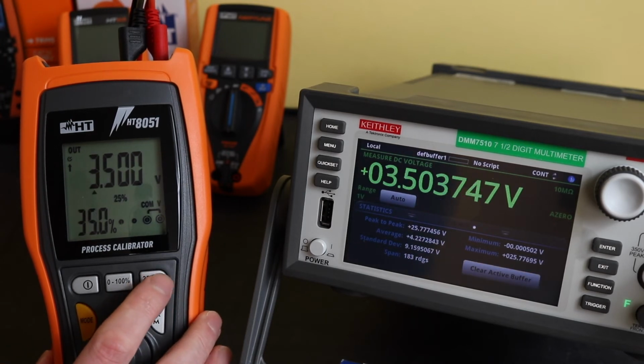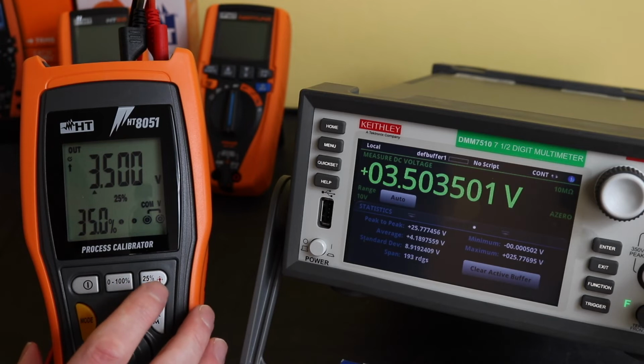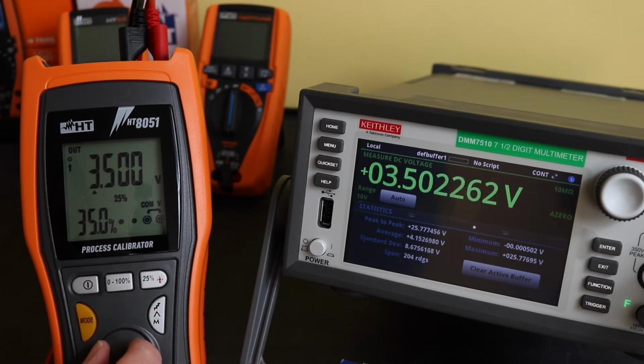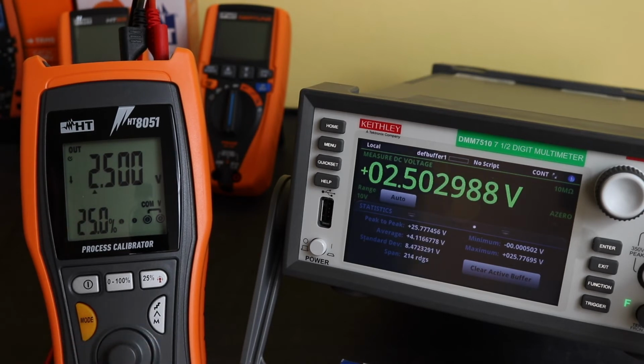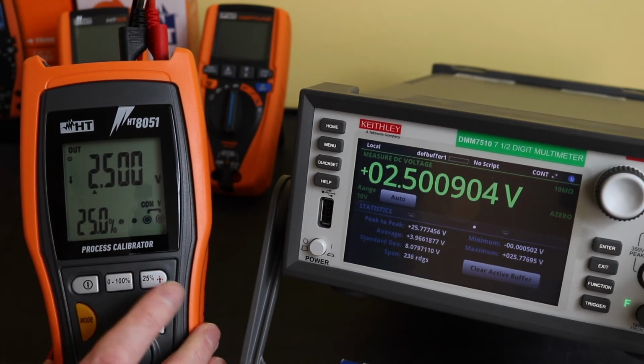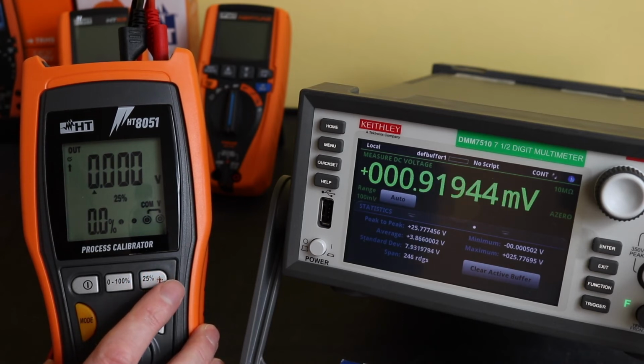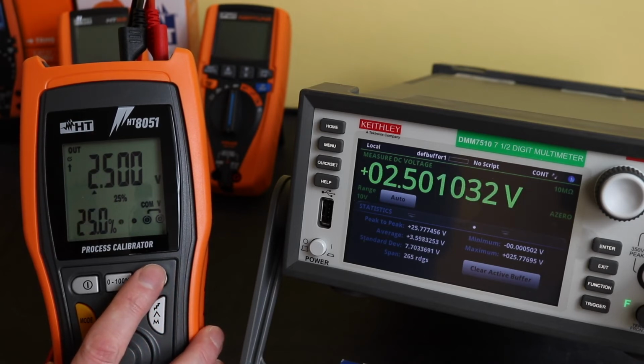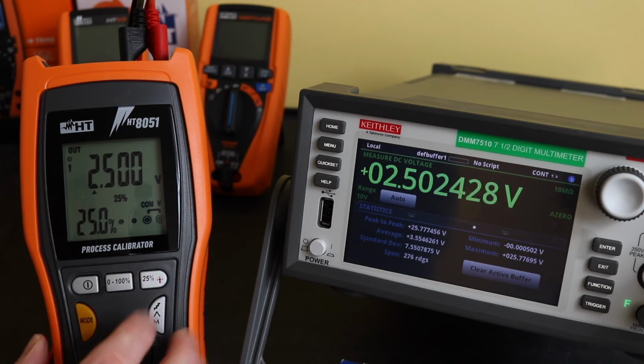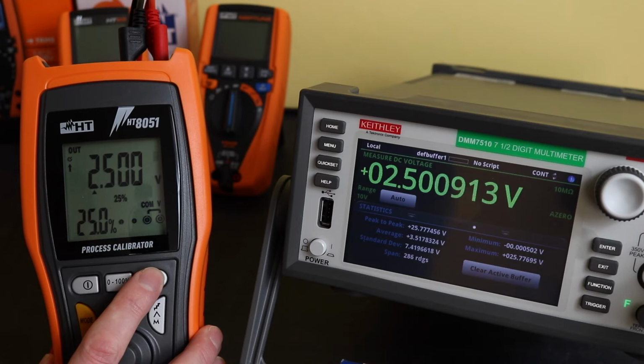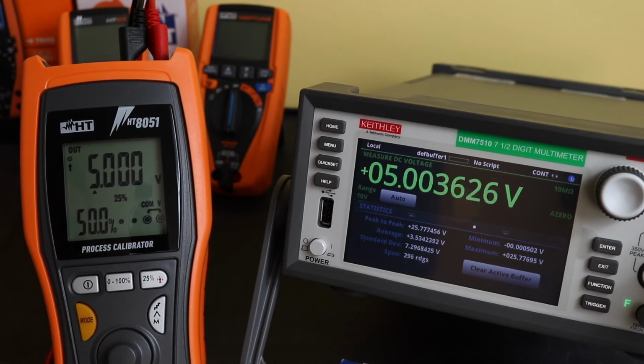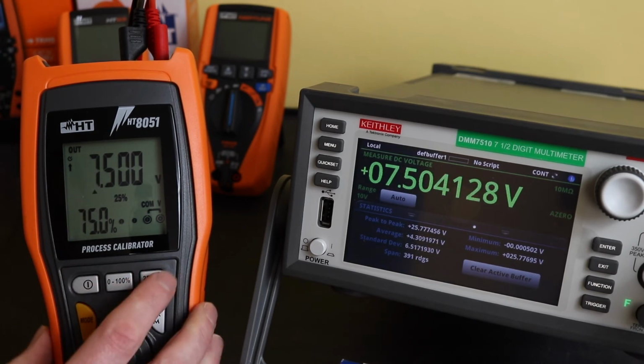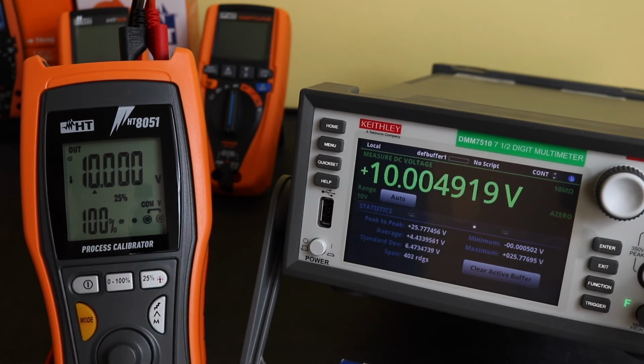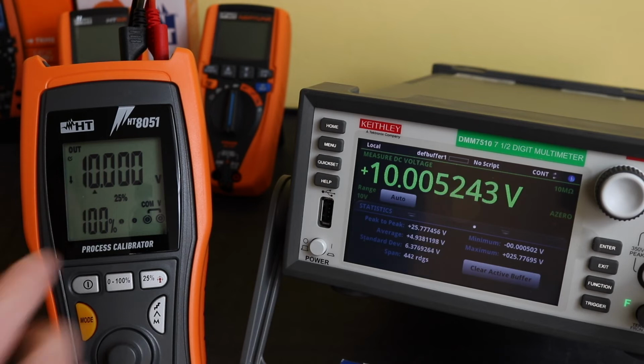And then we'll use our 25% button. Like that, did it? Yes, 25% just adds on. So let's just take them down to 2.5 volts there. And then press them again. Why have we got zeros? That didn't work, did it? Must have changed the direction when I took it from 3.5 down to 2.5. So we've done that one. 5. Another percentage, 7.5. And then final max 100% is 10 volts. Okay, so that's the voltage output.